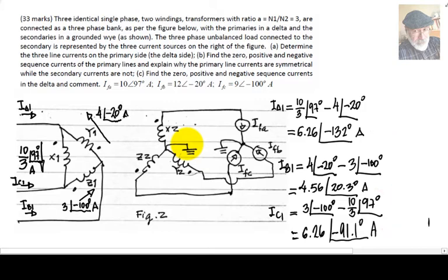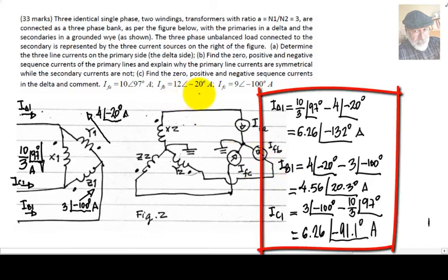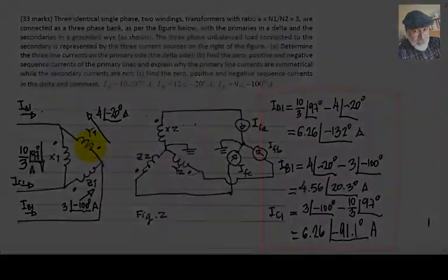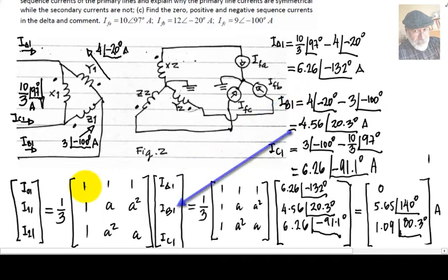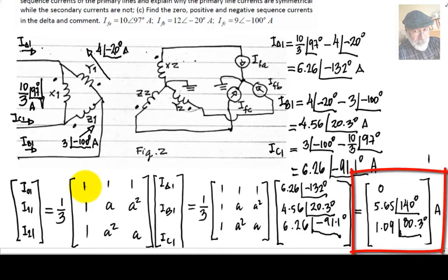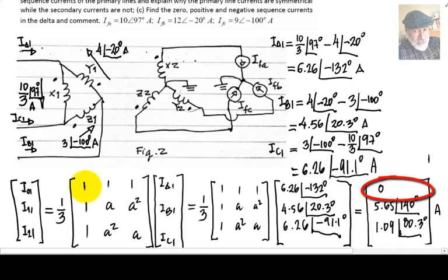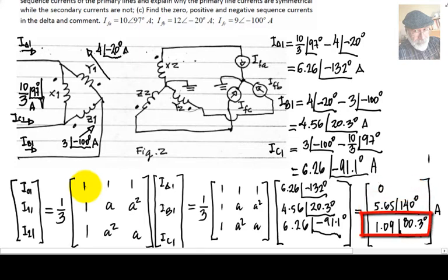That concludes Part A. For Part B, we find the zero, positive, and negative sequence currents of the primary lines by converting these three currents to the sequence domain. We apply the usual transformation to the three values obtained — 6.26 at negative 132 degrees, 4.56 at 20.3 degrees, and 6.26 at negative 91.1 degrees — to obtain the zero sequence, the positive sequence, and the negative sequence of the primary. The zero sequence is zero; there are no zero-sequence amps in the primary lines. There is positive sequence and there is negative sequence. That responds to Part B.